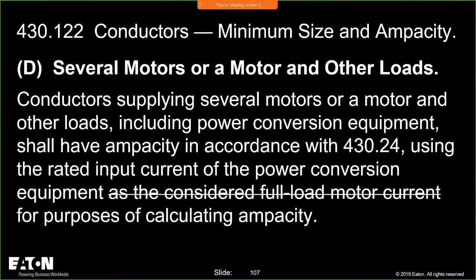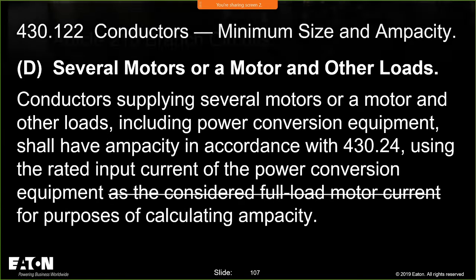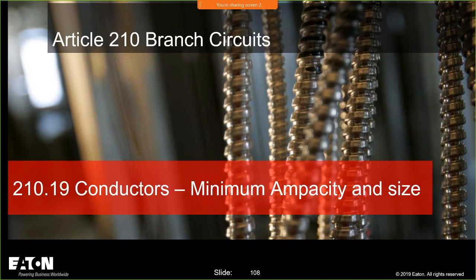Conductor supplying, so again, using the rated input current of the power conversion equipment as the considered full load motor current for the purposes of sizing. They made some changes in this area because the drive equipment is getting better and changing. We have to change these conductor requirements.